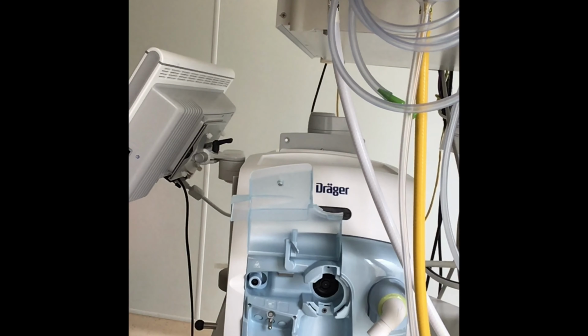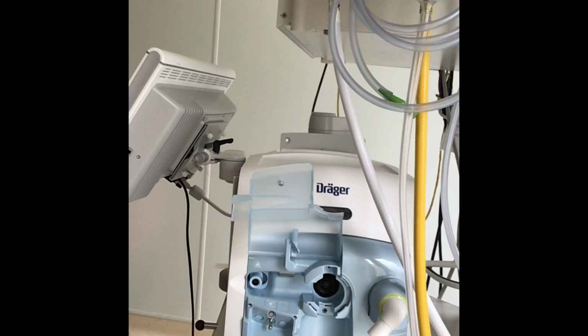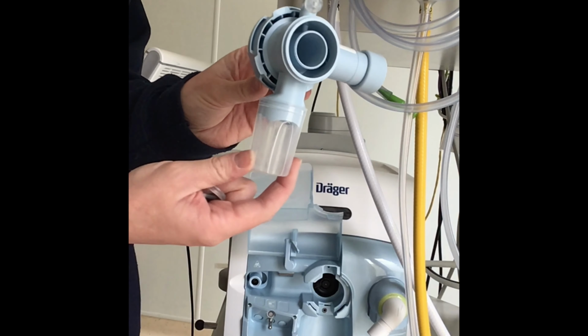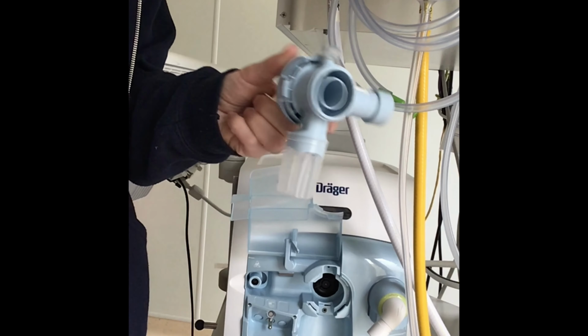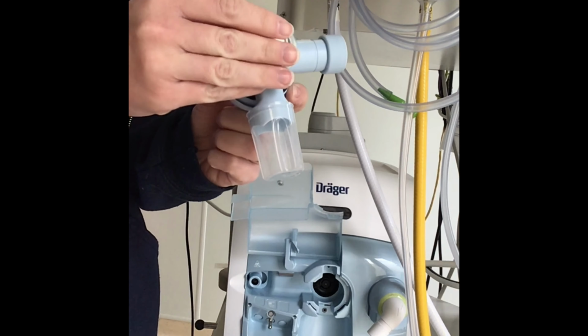This is just a setup for the Draeger V500. Before you put any patient circuit on, you obviously need to fit the flow sensor and also the expiration arm. For the V500, this is the expiration arm that you need, the one with the water trap at the bottom. It's really important when you get it out of the packet that you make sure that this little valve is connected onto the back.